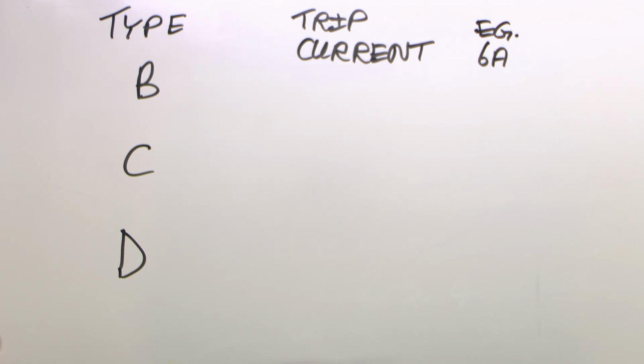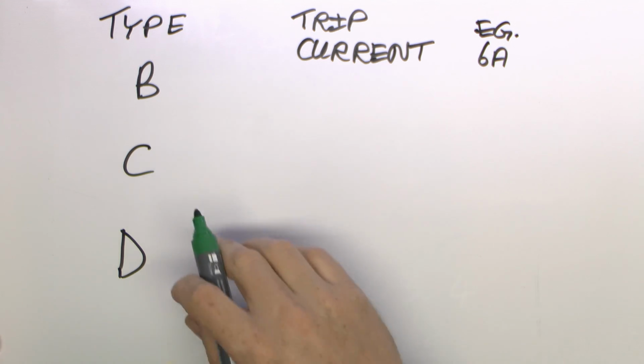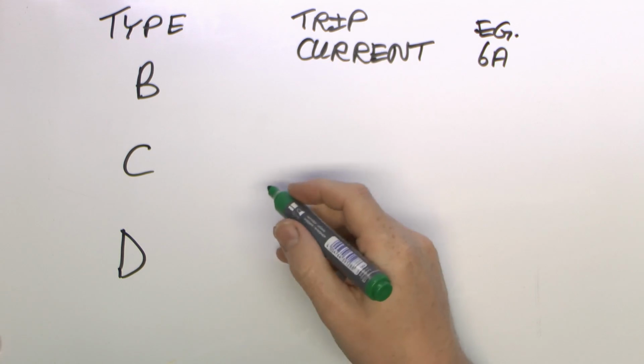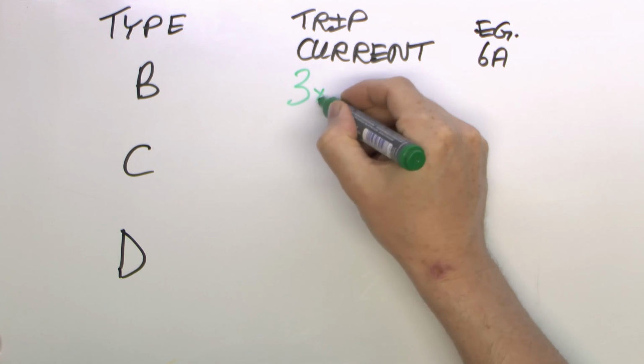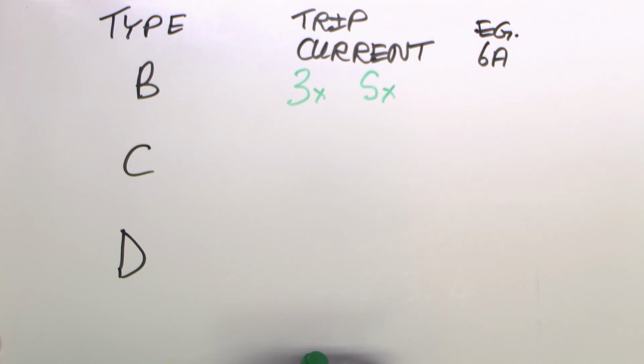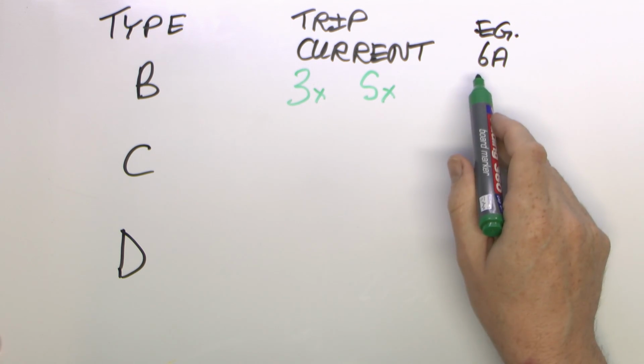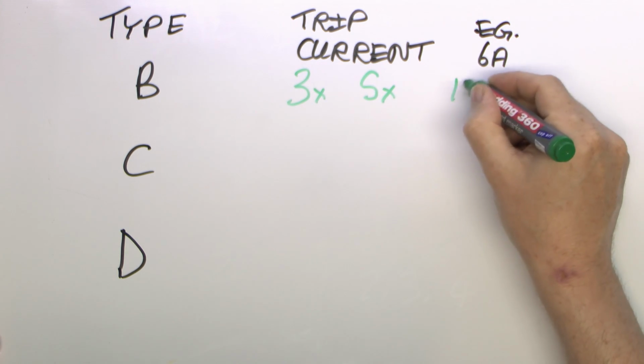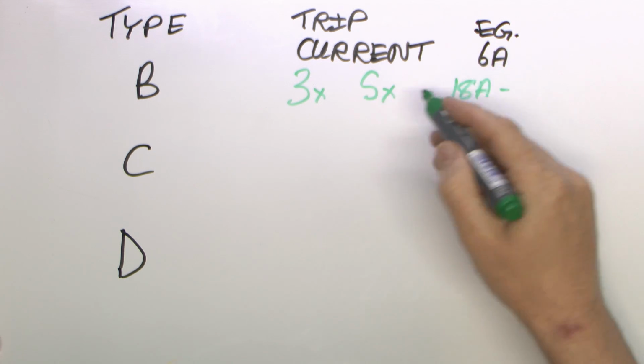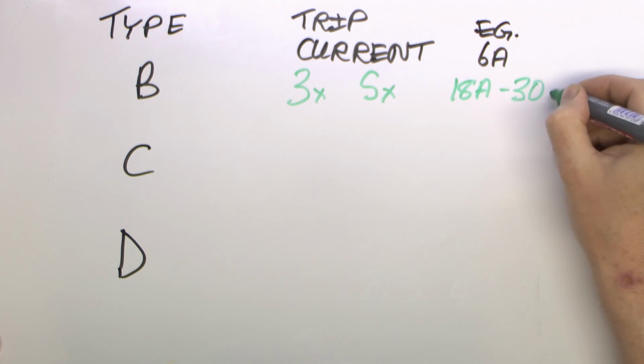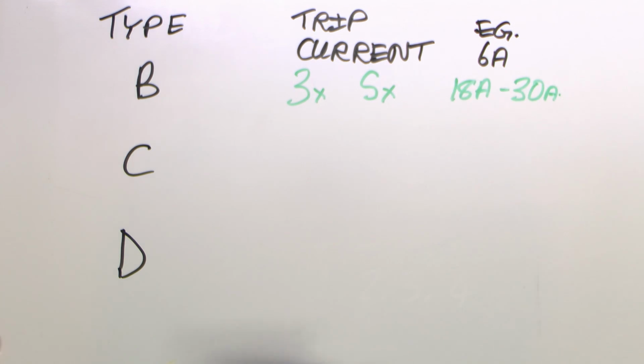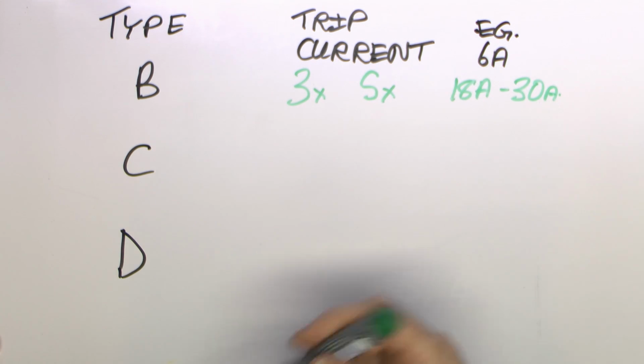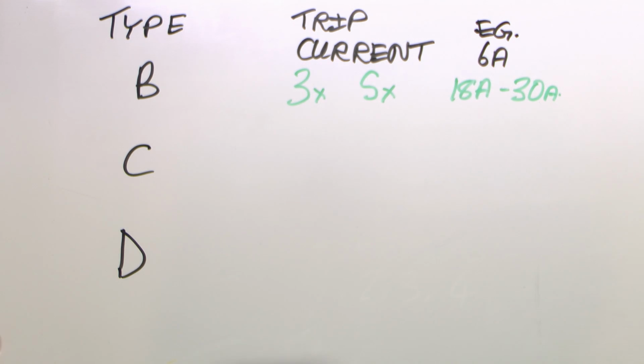And in terms of a short circuit, say for example a 6 amp circuit breaker does not trip when the current actually exceeds 6 amps. And for the Type B, which is probably the more common version, the actual tripping point is between 3 times and 5 times the rated current. So for a 6 amp circuit breaker, 3 times 6 would be 18 amps, and at the upper end of the scale that would be 5 times 6, which of course would be 30. So to trip a 6 amp circuit breaker nearly instantaneously, you would need to apply current of somewhere between 18 and 30 amps to it, not anywhere near the 6.